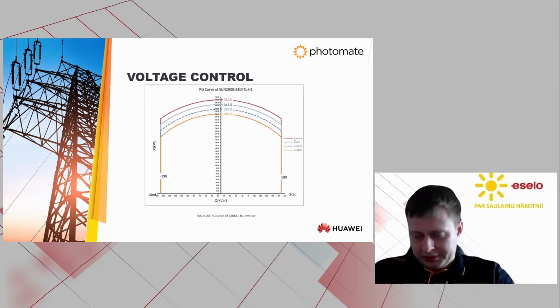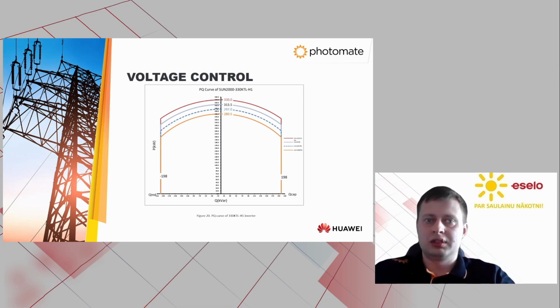An alternative approach to changing the cable to a thicker one is to use a characteristic curve called Q(U). It means that if the voltage rises, the inverter can consume reactive power to decrease the voltage in the grid. This works pretty nicely, but it has one disadvantage. Because the inverter is limited by maximum apparent power, as shown in figure 20, a 330 kilowatt inverter can work at 330 kilowatts if cosine phi equals 1. But if the inverter is consuming or generating some reactive power, the maximum active power is decreased.